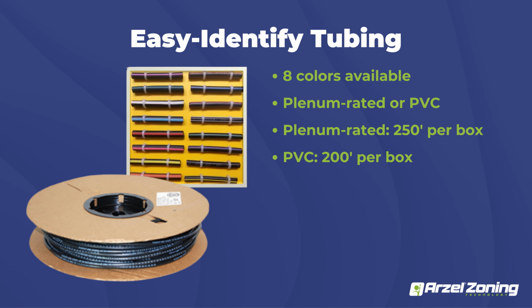Our tubing itself, we have 2 different tubings. So we have our PVC tubing, which is going to be used for any of the EzySlide dampers, whether it be round or the rectangle. That's used for running the tubing outside of the ductwork. Then if you guys get into any of our internal mount dampers, you're going to want to use our plenum rated tubing. It's smoke and fire UL listed, so it's made to actually run in that warm air vent. So just make sure you guys are using the proper tubing for your application.